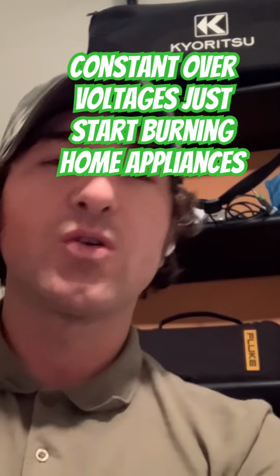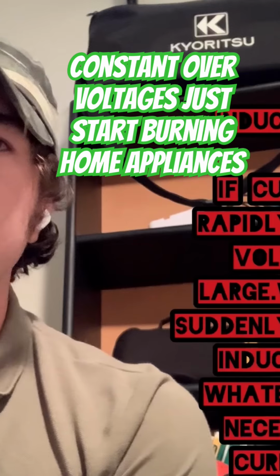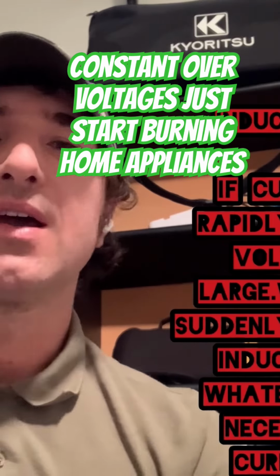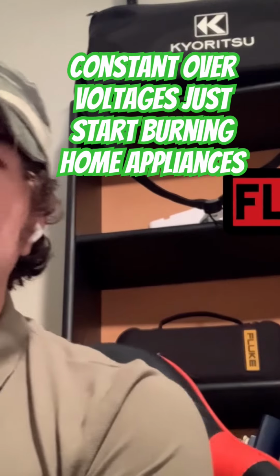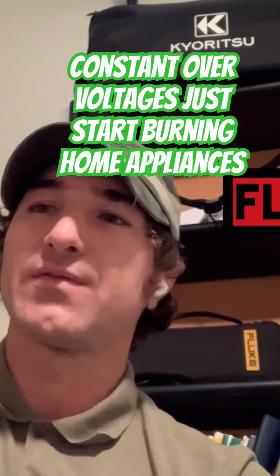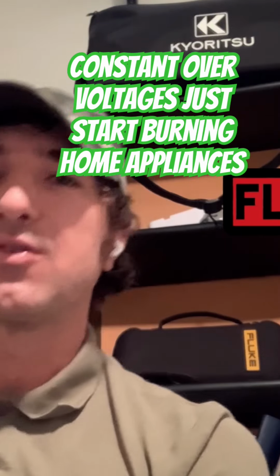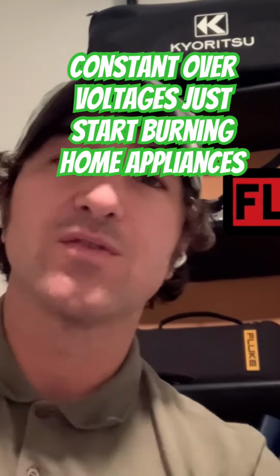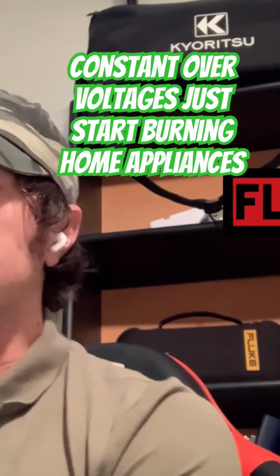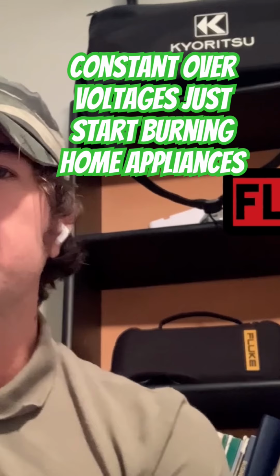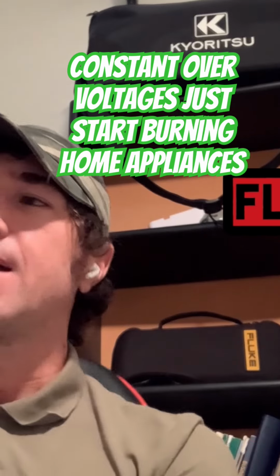Technically, the causes of over voltage: switching loads could cause an increase in voltage. Another would be disconnecting your neutral at the supply kiosk, say in a TNCS system. You could disconnect your neutral, and all your phase voltages, your phase voltage between live and neutral, floats up to like 400 volts. I've seen it, and it pops things.